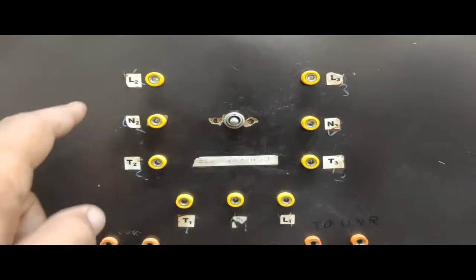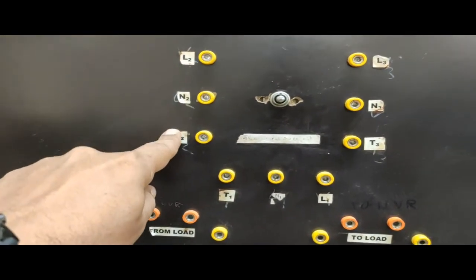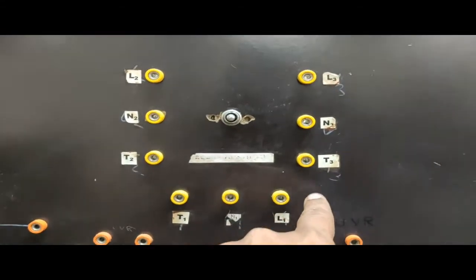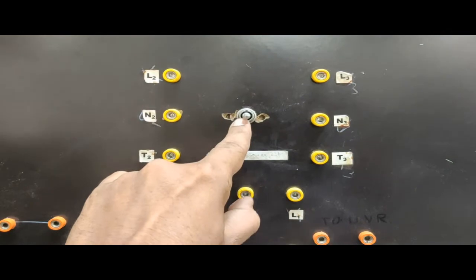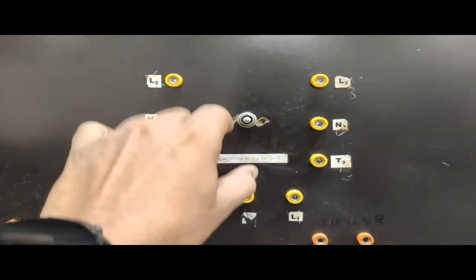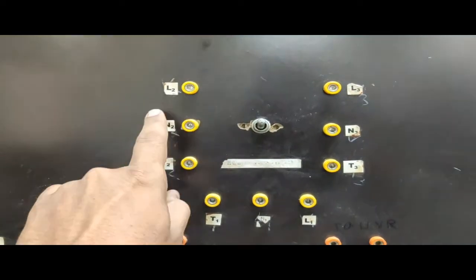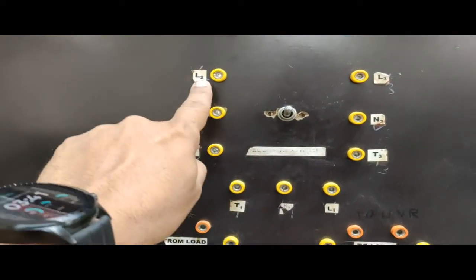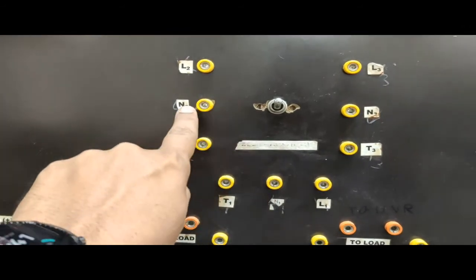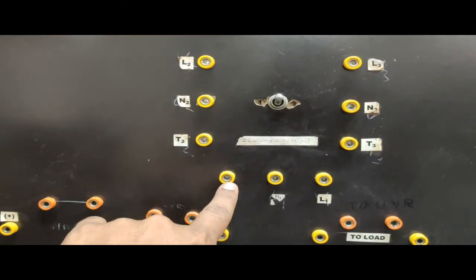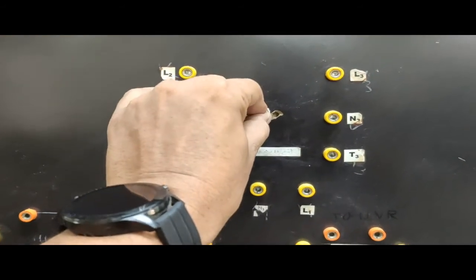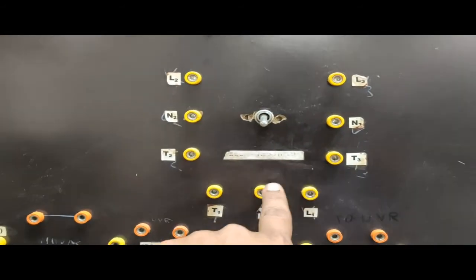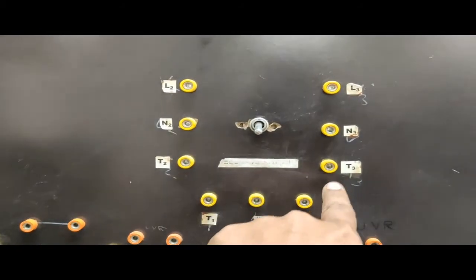So let's identify the switch. This is a 3-pole two-way switch. That means here you see three terminals, L, N, T, also L and T, also L and T. Now if the switch is in the middle position, then all the terminals are disconnected from each other. If I move the switch to the upward position, then this side's terminals are connected to that side. That means L2 will be connected to L1, N2 will be connected to N1, T2 will be connected to T1. And if I press the switch in the downward position, then these side terminals are short circuited with that side, I mean L2 to L3, N2 to N3, T2 to T3. So this is the switch.